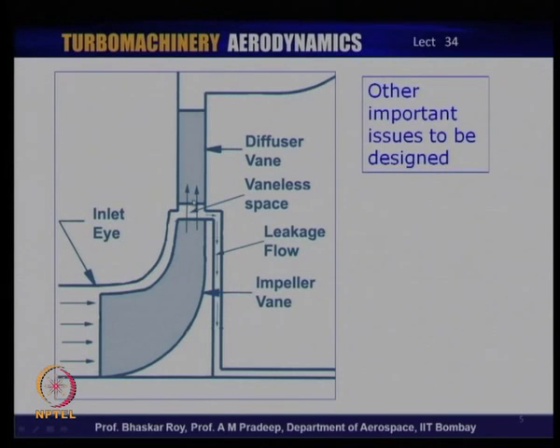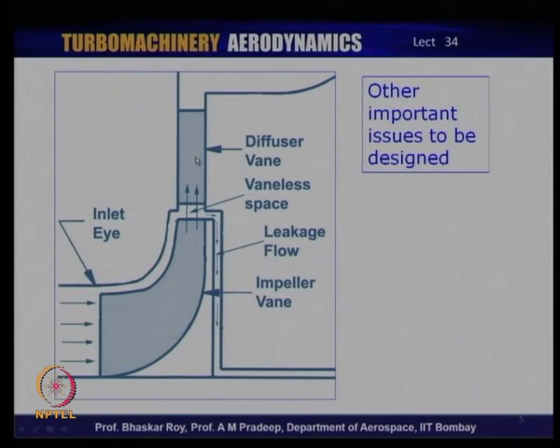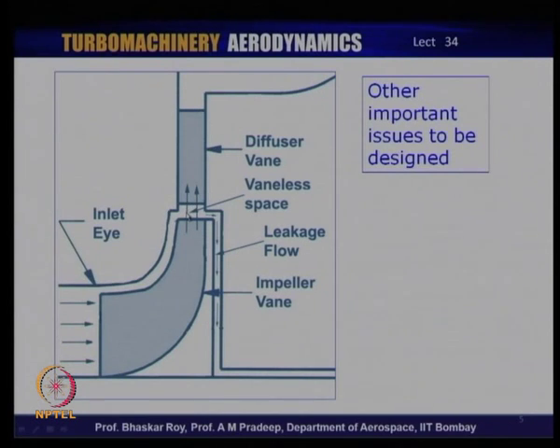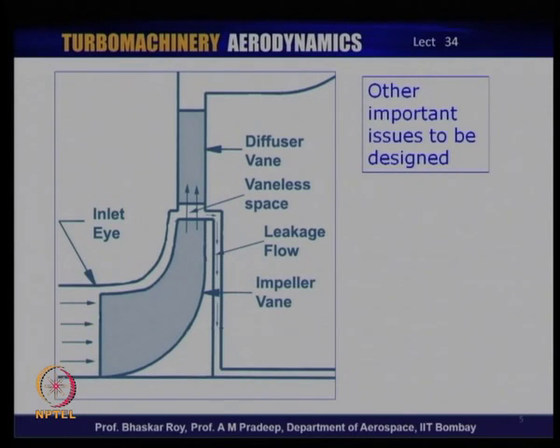All around the impeller there has to be a small gap, and one has to decide how much this gap should be — because the gap facilitates leakage of flow, which is a loss to the machine in terms of compressing work. The other thing that has to be decided is the vaneless space invariably provided between the impeller and the diffusing vane. The diffusing vane converts kinetic energy to pressure, and this vaneless space is a hugely important element. The rotor needs to be separated from the stator, but this vaneless space is also used intelligently to control the flow going from rotor to stator — reducing losses and ensuring the flow is guided in a manner that avoids stall, surge, and supersonic flow related problems.